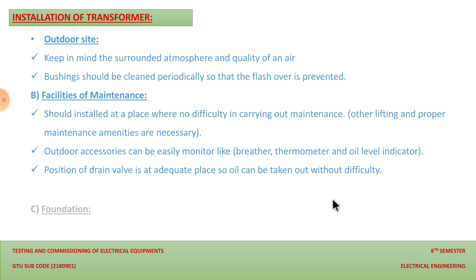So there will be no difficulty taking out samples of the oil to check its dielectric strength. And the third point is the foundation. So the foundation must be proper. A simple foundation is sufficient for a static machine, because a transformer is not a rotating machine and will not vibrate like one. So a simple foundation is adequate, and a strong, leveled, and dry foundation is advisable for the transformer.